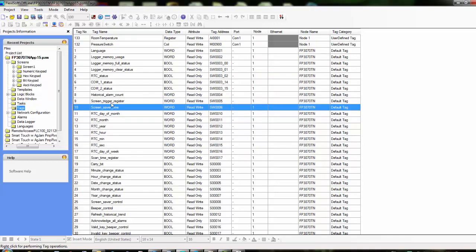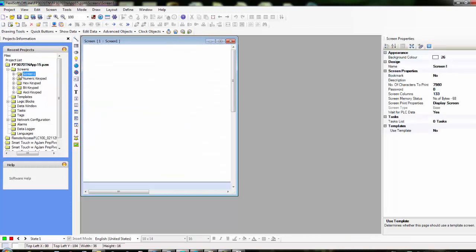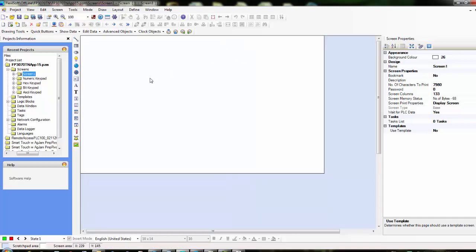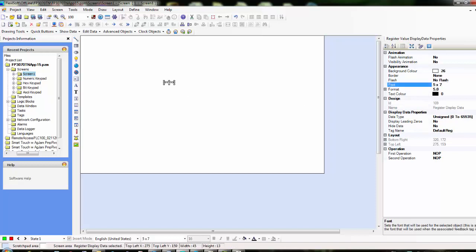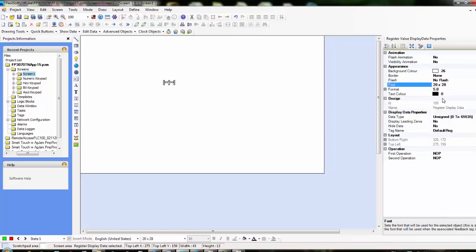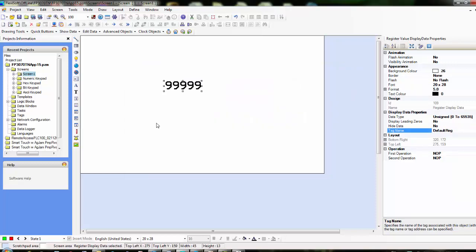If we wanted to display one of these variables, we can just bring up a screen. This is the base screen that it creates. Then all we would do here is show data—it's a numerical data point. We can change the size of this data point. To declare that we want to show that tag, we can just click on tag name, go to the database, and click on room temperature. So now at this point, the HMI is going to be reading in that temperature from the GE PLC. It's just a brief introduction to how you can do different protocols, and in this case, we did the GE.